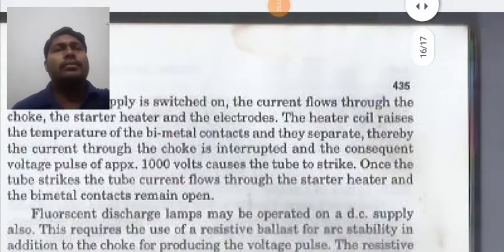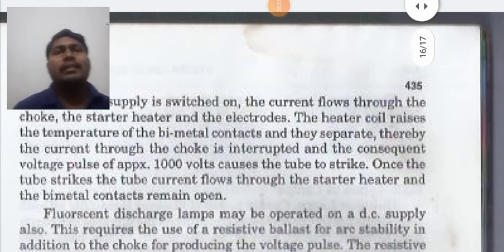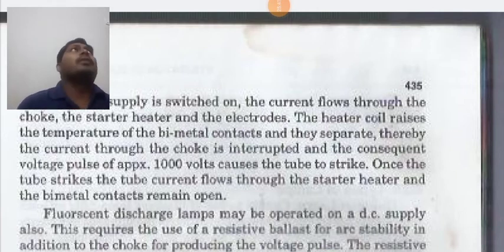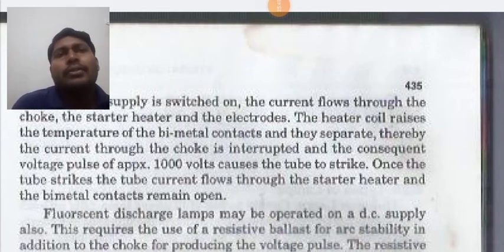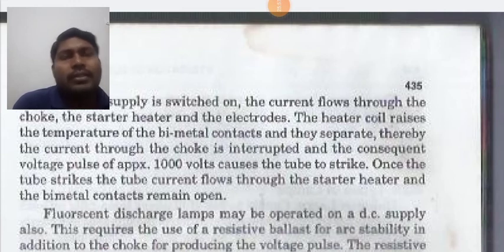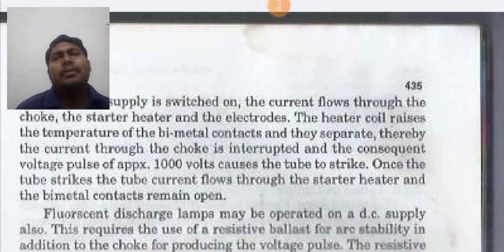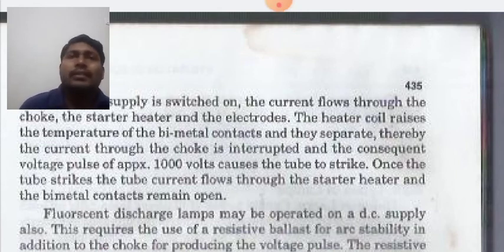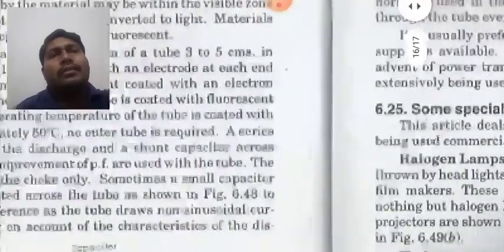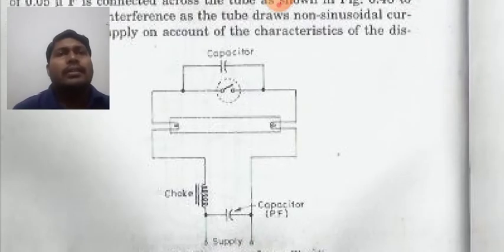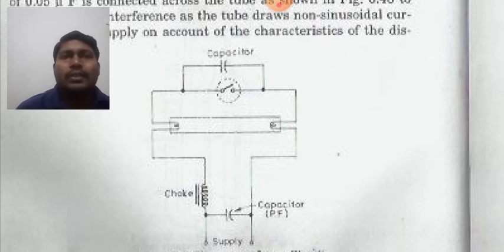When the supply is switched on, the current flows through the choke, the starter heater, and the electrodes. The heater coil raises the temperature of the bi-metal contacts and they separate, thereby interrupting the current through the choke. A voltage pulse of approximately 1000 volts causes the tube to strike. Once the tube strikes, the tube current flows through the starter heater and the bi-metal contact remains open. The circuit diagram includes a choke, a starter, and a capacitor connected for correcting the power factor.